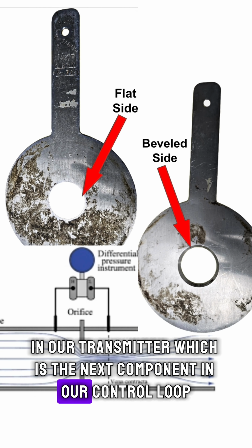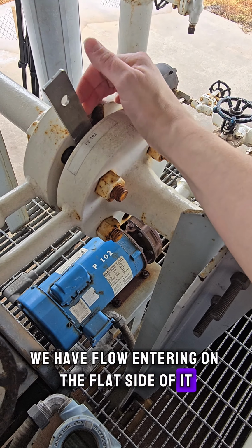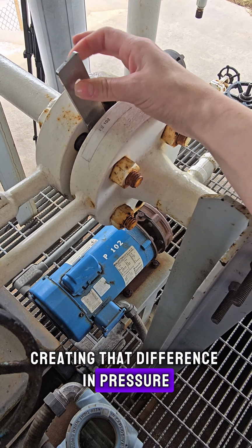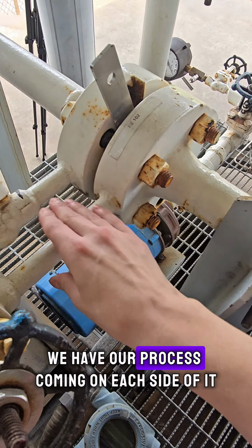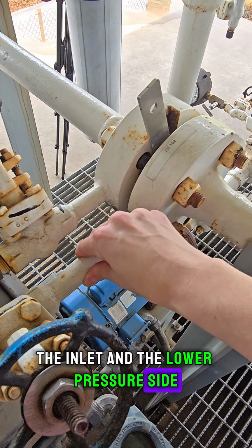Here we have our flow element, which is our orifice plate. It's in between two flanges. We have flow entering on the flat side of it, creating that difference in pressure. We have our process coming on each side of it. These are our two legs. This is going to be the higher pressure side, the inlet, and the lower pressure side, the outlet of the orifice.